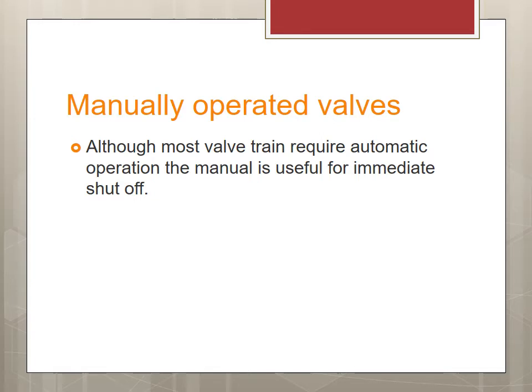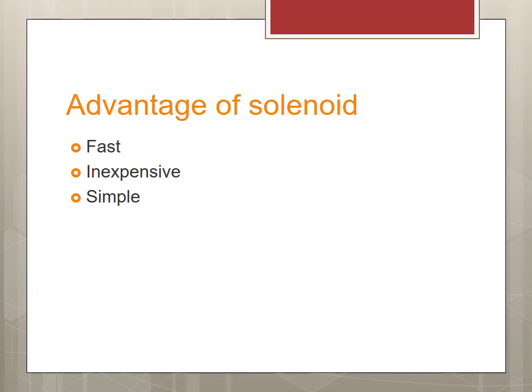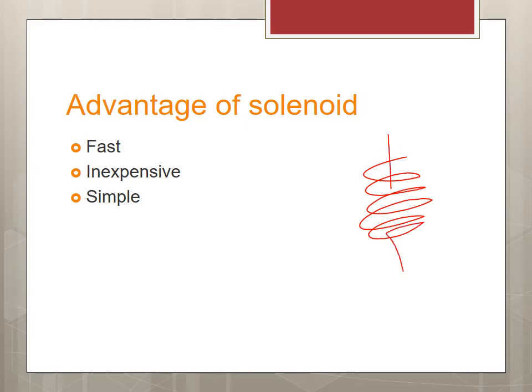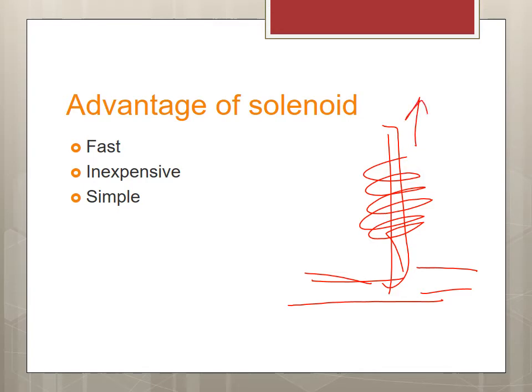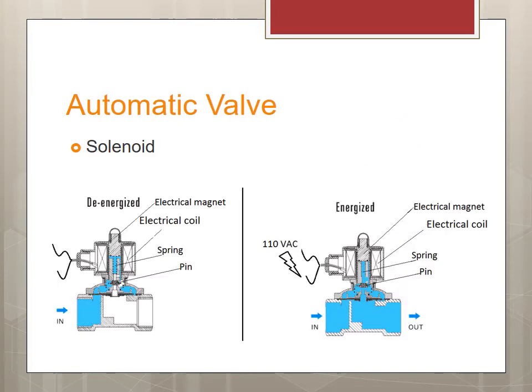The solenoid valve is very fast, inexpensive, and very simple — it's either on or off. We control a coil; that coil controls a pin, and this pin shuts on or off the fuel. Once we energize the coil the pin goes up; when de-energized it drops and stops the fuel. Depending on the fuel pressure, it's important to control the pressure of this pin dropping, and you want a very small amount of fuel flowing through this valve.